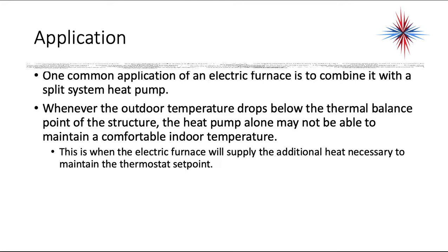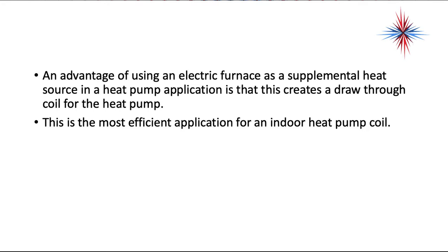One common application of electric furnace is to combine it with a split system heat pump. We haven't talked about heat pumps yet, but heat pumps are reversible air conditioners. Whenever the outdoor temperature drops below the thermal balance point of the structure, in other words, the temperature that the heat pump can still provide heat to the building, the heat pump alone may not be able to maintain a comfortable indoor temperature. This is when the electric furnace will supply additional heat necessary to maintain the thermostat set point. One advantage of using an electric furnace as a supplemental heat source in the heat pump application is that this creates a draw through the coil for the heat pump. This is the most efficient application for an indoor heat pump coil.